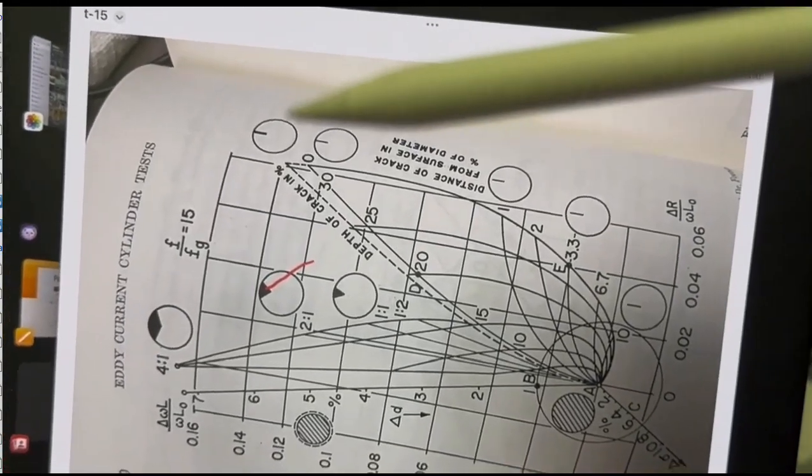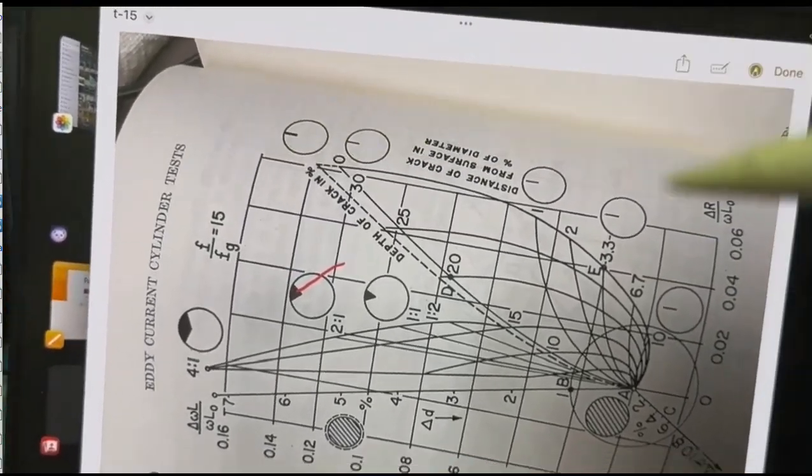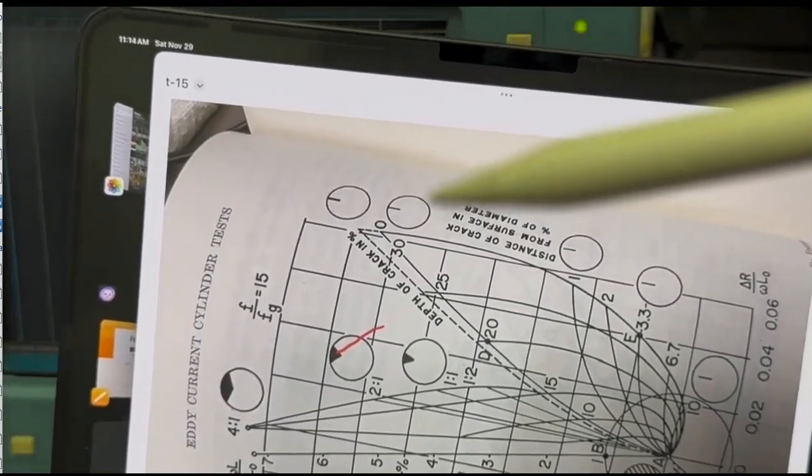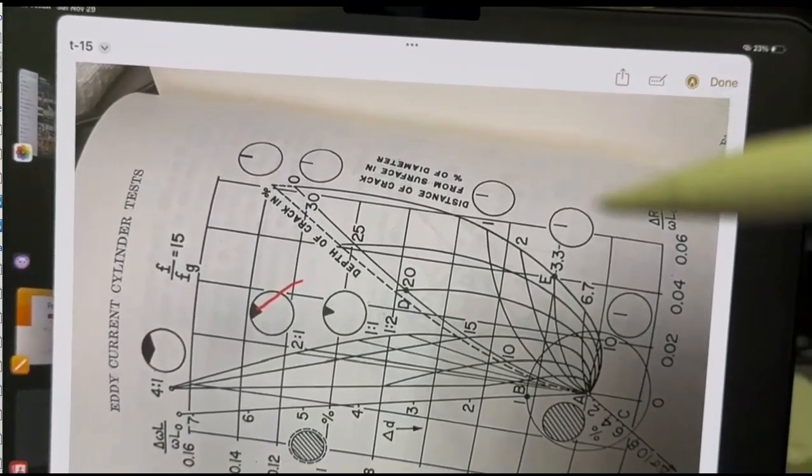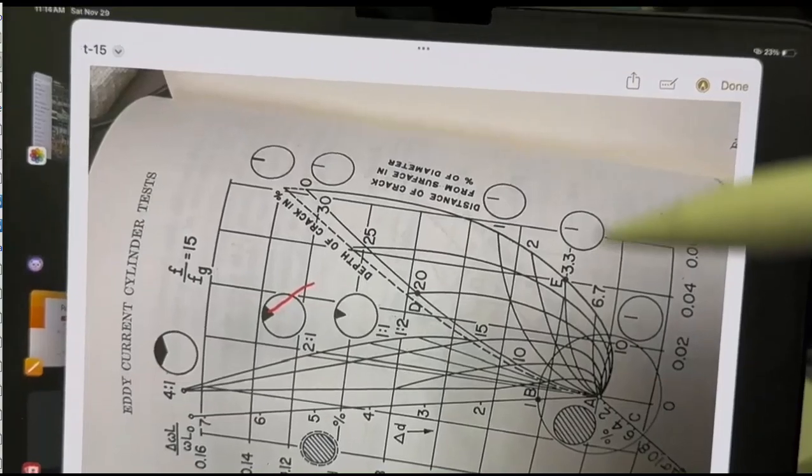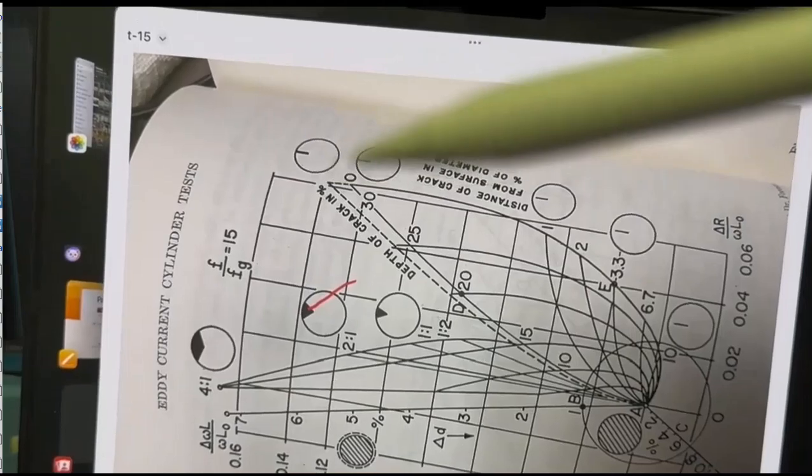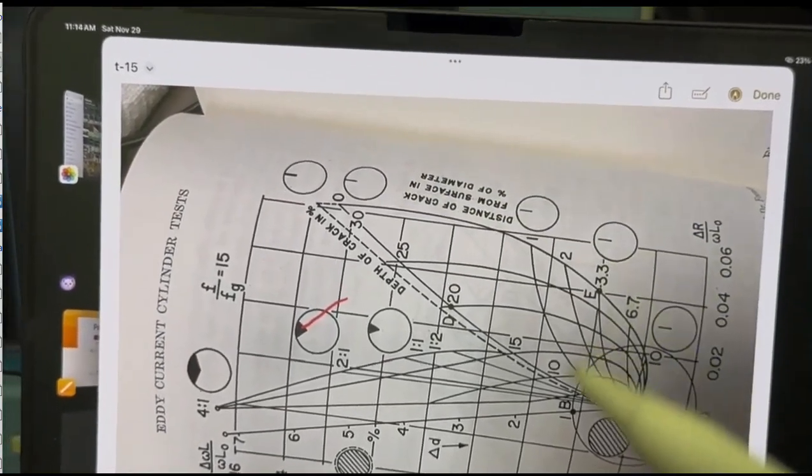And you've got a notch open to the surface. Get a great big signal here. This one right here. Then you get that same notch moved a little bit below the surface. Then you got it a little bit more below the surface and quite deep subsurface there. So you see the amplitude of the signal as well as the phase changes as you drop below the surface.